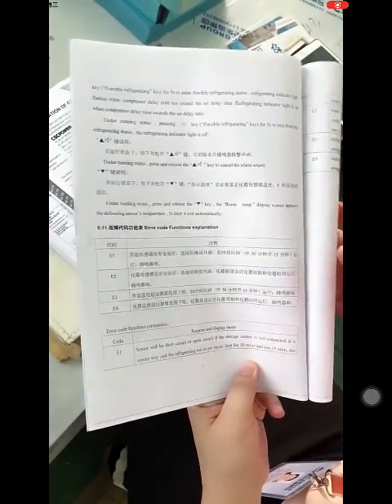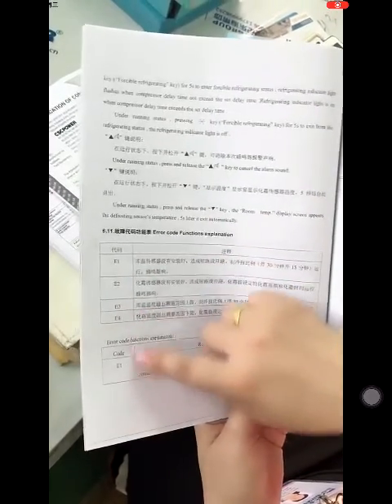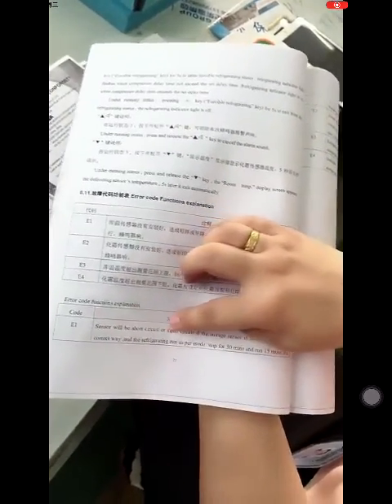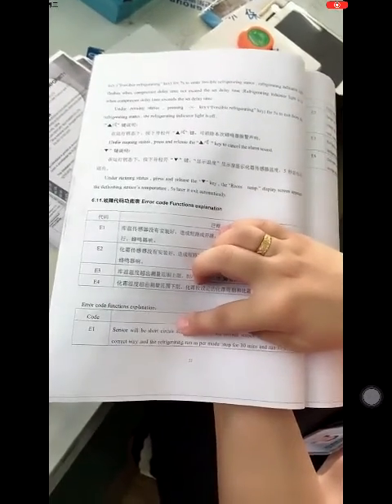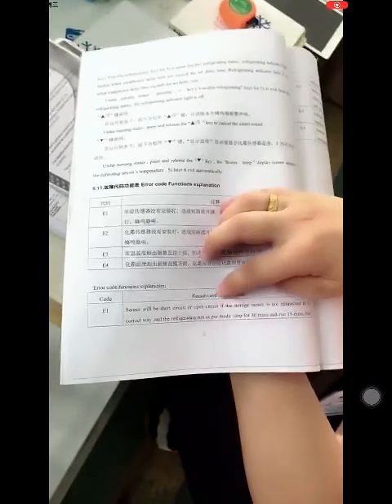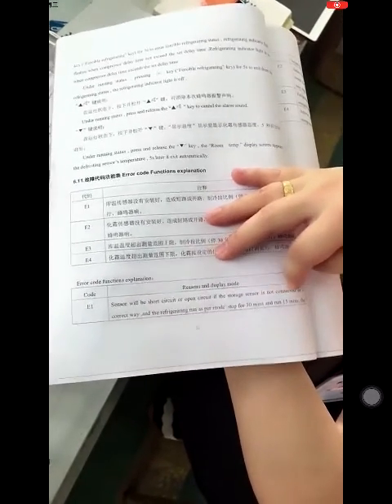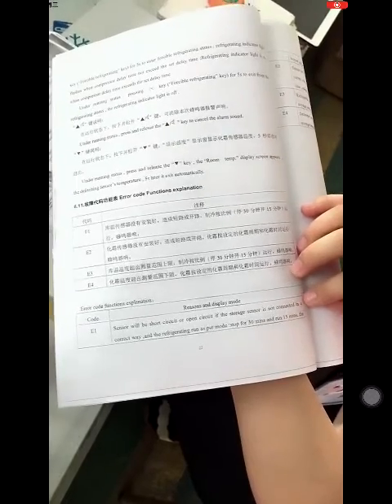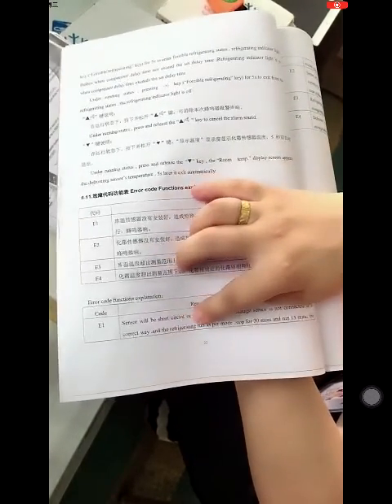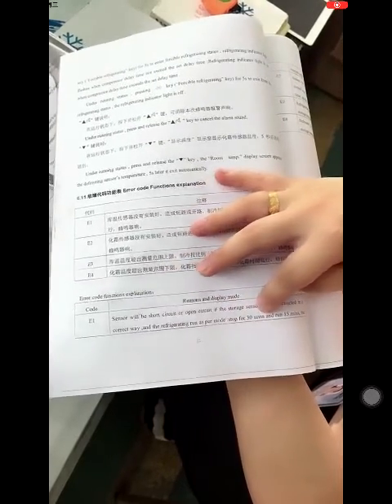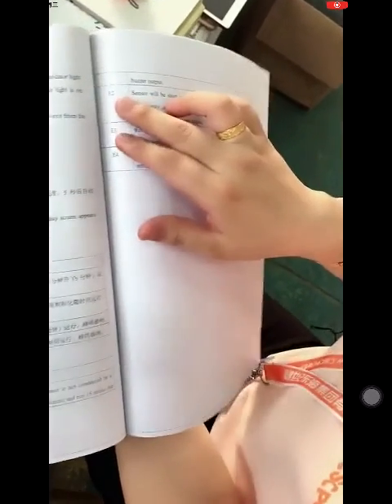Here is the error code. In case there are any problems, you can identify them through these error numbers. For example, E1, E2, E3, E4 have different meanings. E1 means sensor short circuit or open circuit, if the storage sensor is not connected in a correct way, and the refrigeration runs as per mode: stop for 30 minutes and run 15 minutes. You can see these errors and know what the meaning is and how to solve it through here.